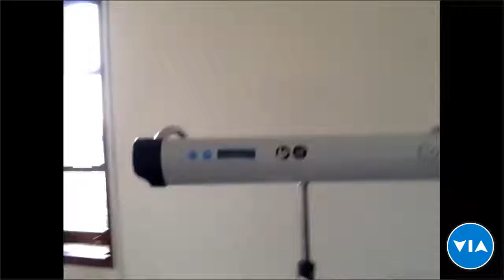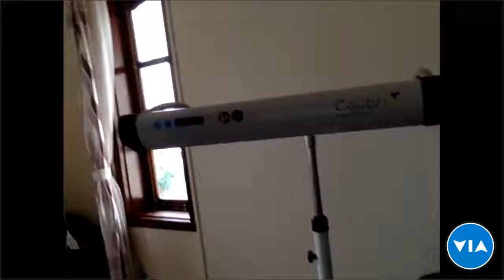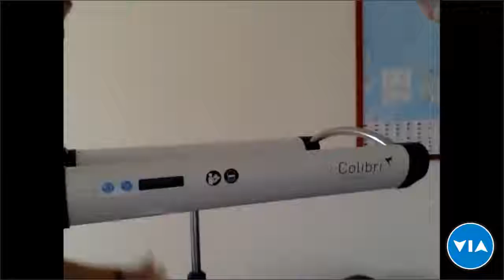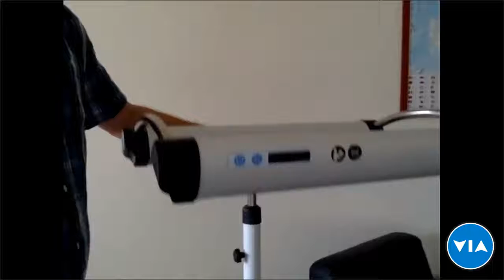For that reason, we have also developed quite traditional or standard therapy, overhead phototherapy, that can be used in any situation and with any other devices, and it's compatible with most of, if not all, incubators and infant warmers. It means that the size of the wheels is to fit underneath the warmers and incubators. The height is also limited not to go too high and too low for the other devices. So we can adjust it up and down accordingly, and you don't have to adjust the angle.